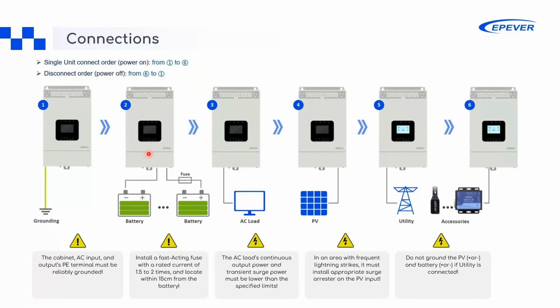After grounding, we go for the batteries. We need to protect the batteries with a fuse, and this fuse is almost 1.4 to 1.5 times the system's rated current; higher than that means abnormalities. Of course, lithium batteries have their own protections and will cut off, but if lithium is not used, then we'll need to implement an external fuse for that.